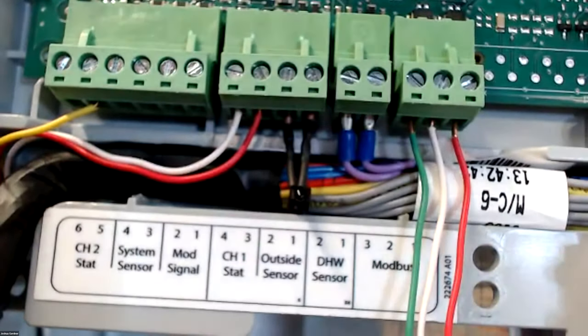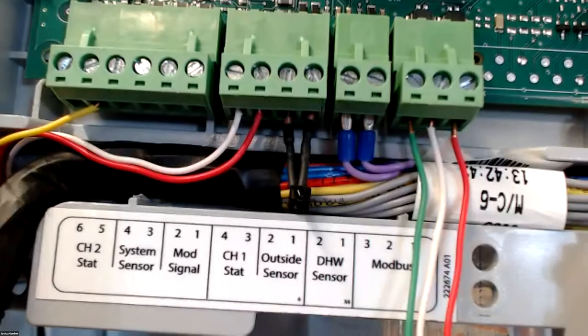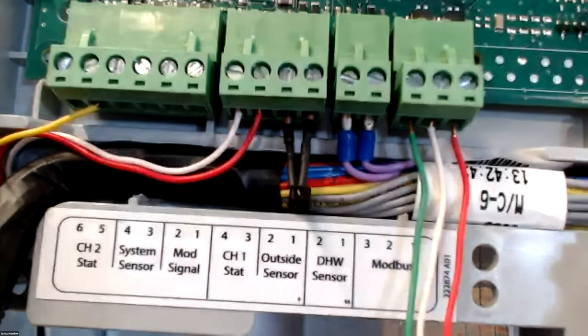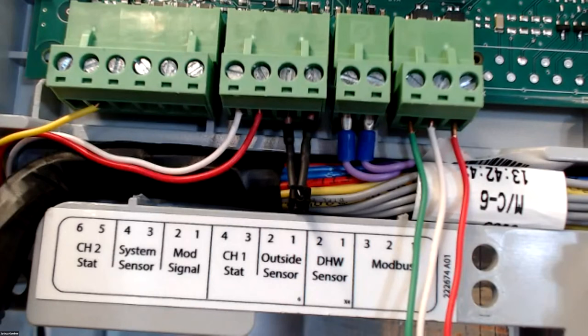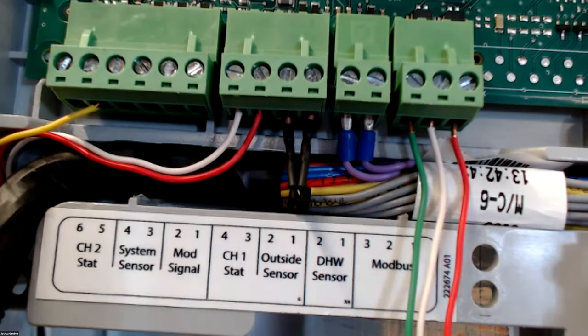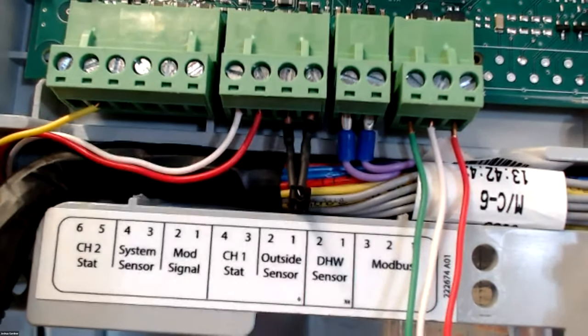When we go through the outdoor reset, you'll see that the outdoor temperature is important to make sure this boiler is firing at the correct temperature for our design. So the outdoor sensor, for most applications, we're gonna need that mounted on the north wall. We want it away from the sun. That sun can throw it off pretty drastically. And if we throw it off, the boiler thinks it's warmer than it is and runs cooler. And then we have a call from the homeowner saying, the thermostat's set at 72 and it's 69 or 70. My house isn't heating. And then you go back and what do? Most contractors just unplug it and call it a day. So making sure that outdoor sensor is installed out of the sun properly is good.